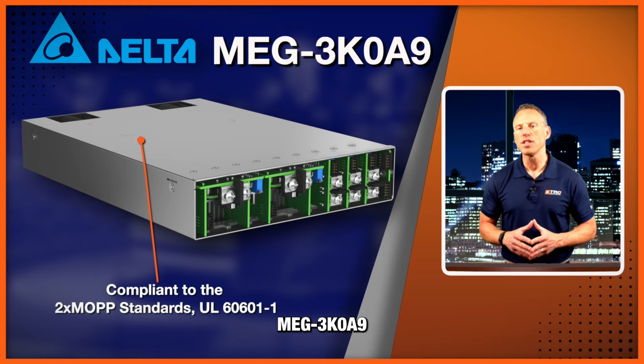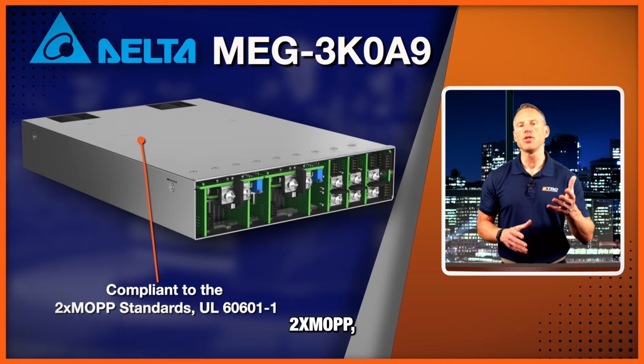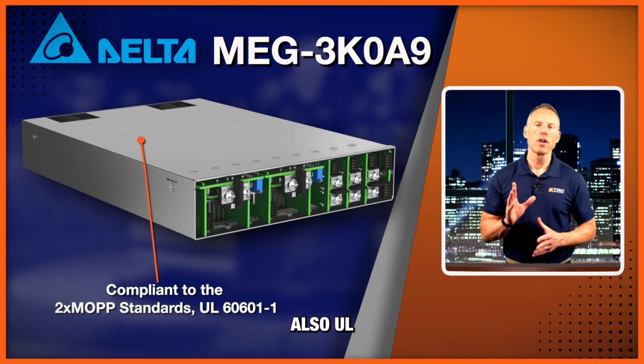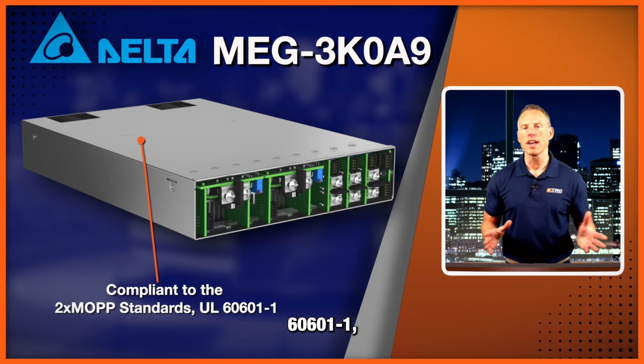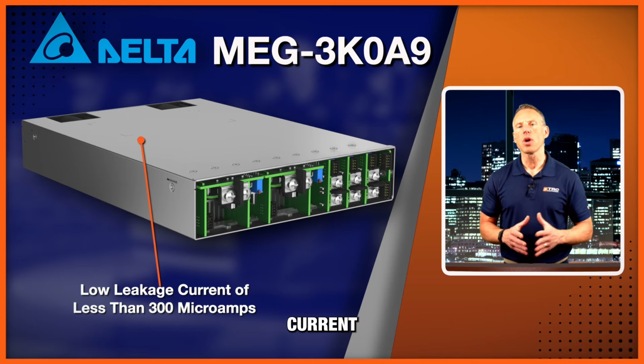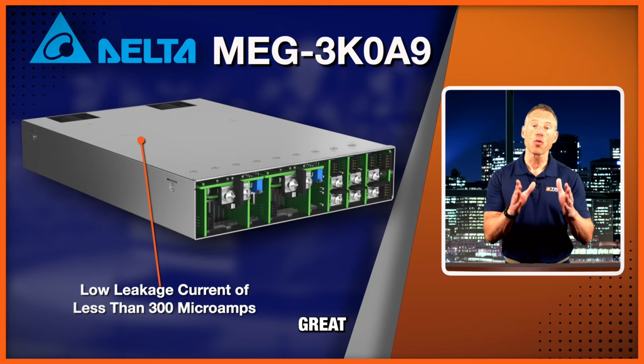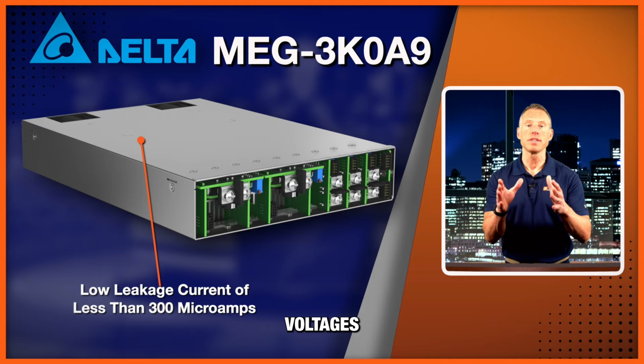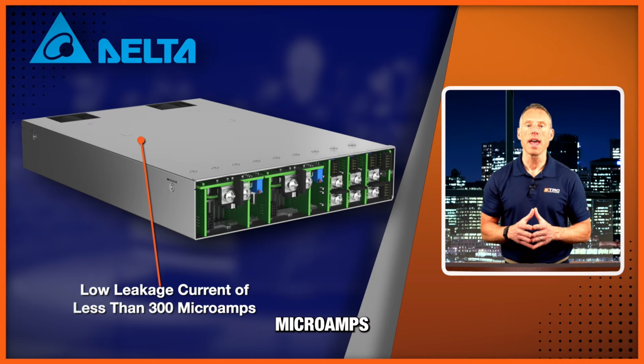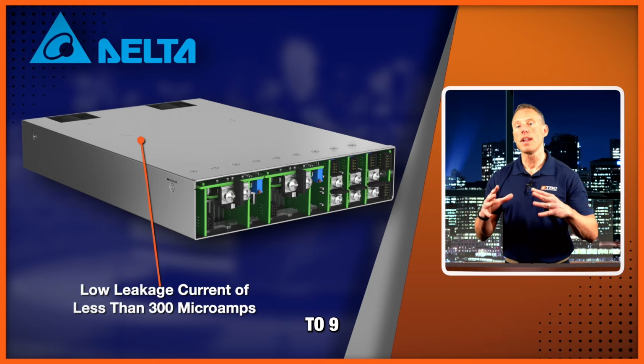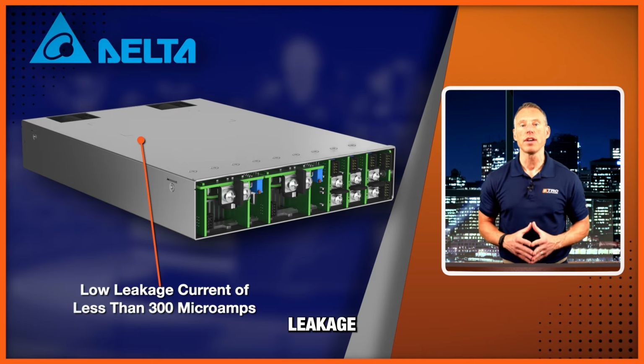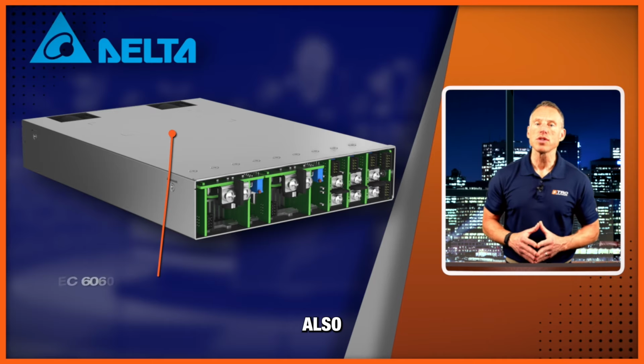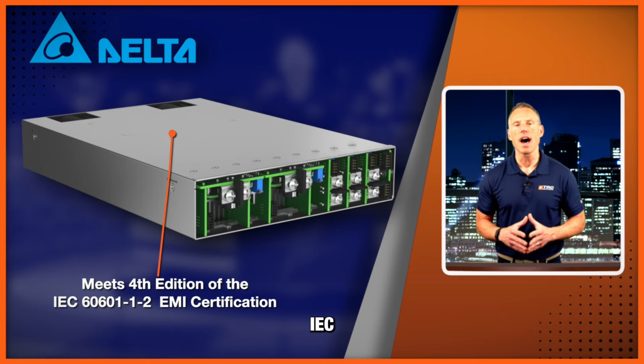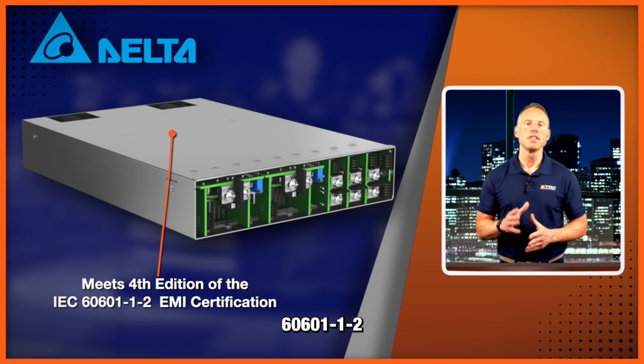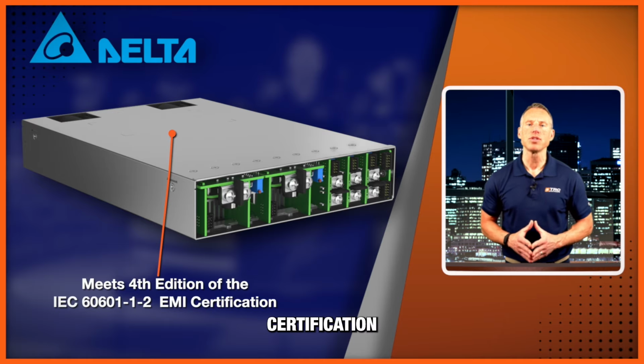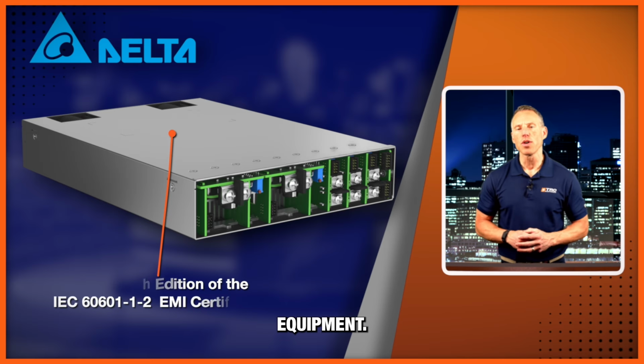The MEG-3K0A9 complies with 2x MOPP, also UL 60601-1, and it has a low leakage current of less than 300 microamps, which is great because you have 9 output voltages and only 300 microamps of leakage current, as opposed to 9 different output power supplies with a lot of leakage current. This unit also meets the latest 4th edition of the IEC 60601-1-2 EMI certification for medical equipment.